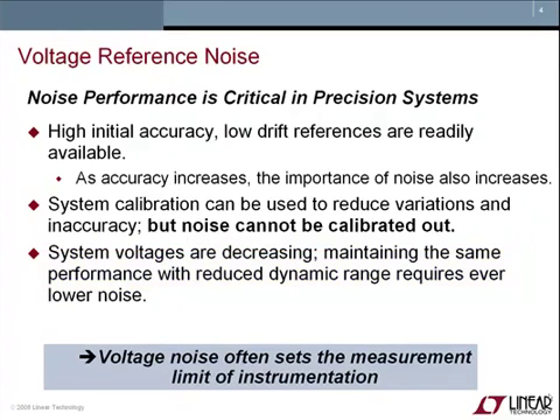For high-performance test and measurement equipment, noise may be, and in some cases is, the most critical parameter for a number of reasons. First, high initial accuracy and low drift voltage references are becoming readily available. For accuracy to increase, the size of the smallest signal that can be resolved decreases, and so the relative importance of noise in the system increases. Secondly, system calibration can reduce some sources of instability, such as initial accuracy and even temperature drift. However, noise cannot be reduced through calibration. Third, electronics are continuously moving to lower system voltages. With lower voltages, noise must also decrease by a commensurate amount to maintain the same level of performance. Thus, it is often the case that voltage noise sets the measurement limit of electronic instrumentation.